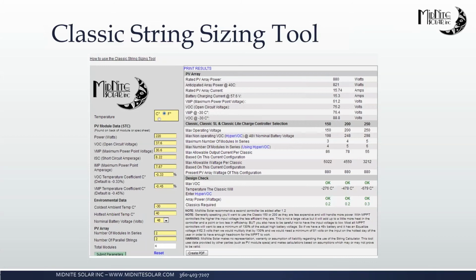Yeah, and to expand on that, Sue, I didn't think to mention it in the Classic String Sizing Tool, but generally speaking, we always want to use the lowest voltage controller that we can use because it's going to be more powerful and usually less costly. And the closer we keep the input voltage to the battery voltage, the more efficient the electronics will be. And those two statements are true for any charge controller on the market. I'm not talking specific to MidNite here. So with that all being said, it's always a balance between PV voltage, wire size, and distance and cost.